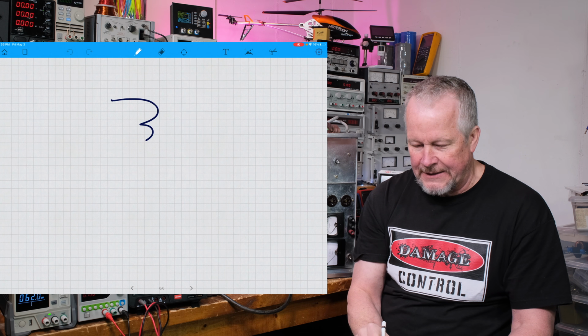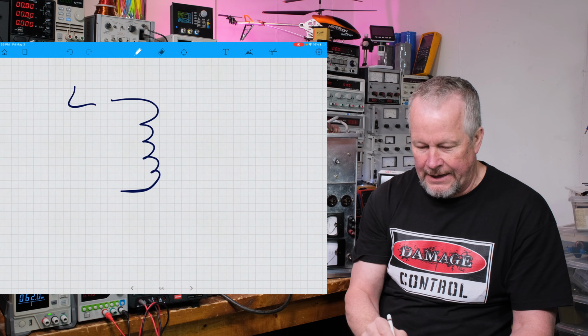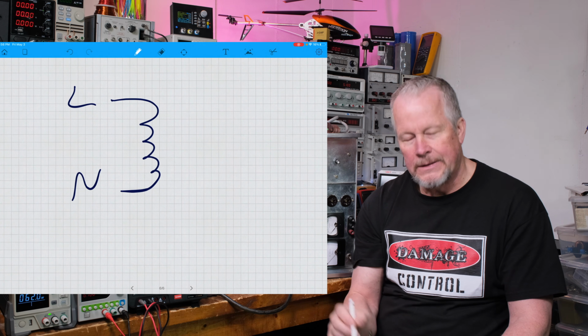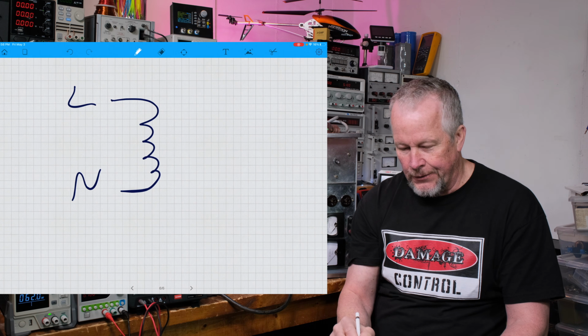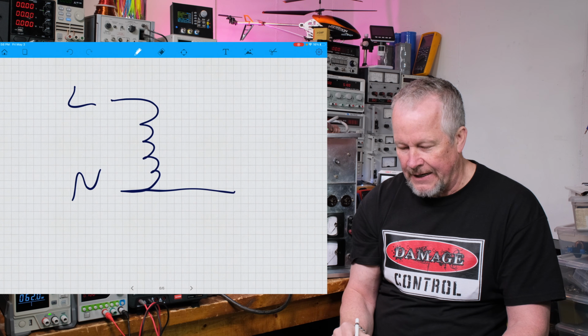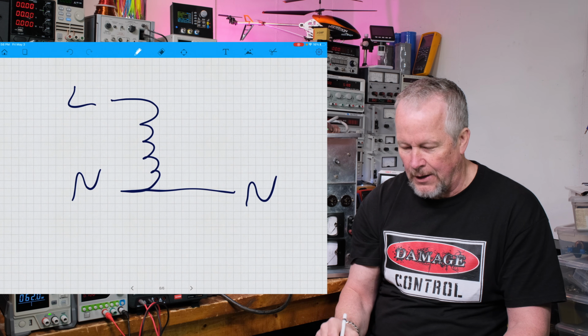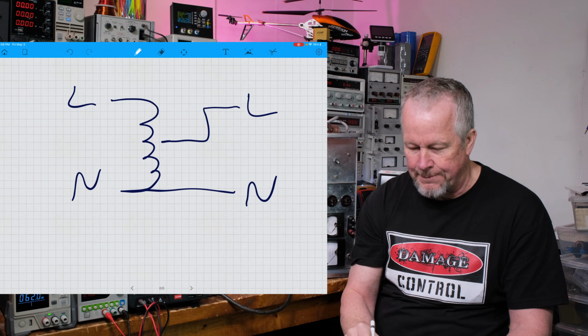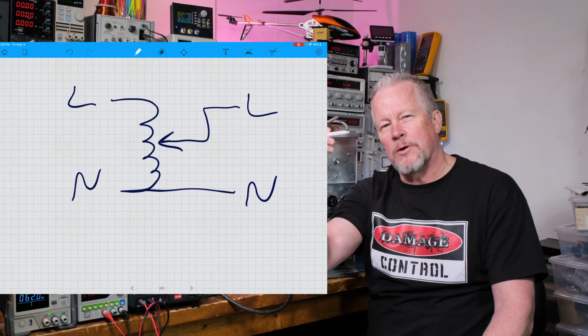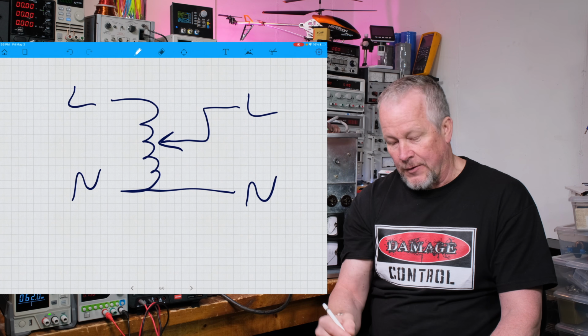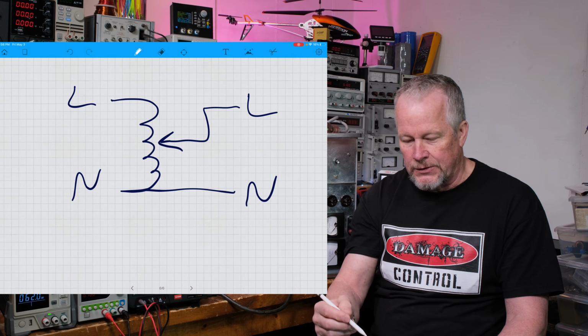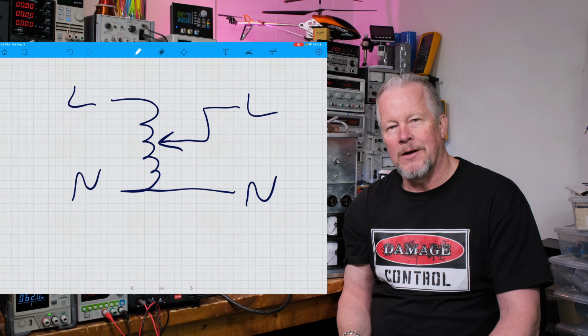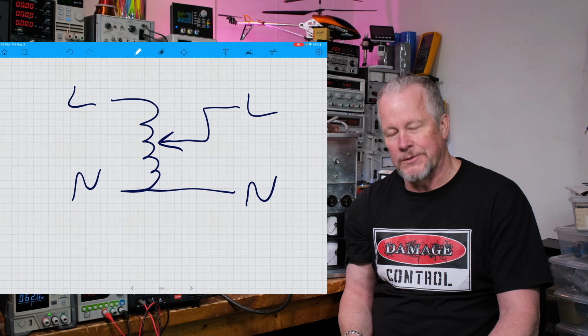Let me show you. It has a winding like this, and you have line and neutral. On the secondary side, where you take your power off, you have neutral, and line here is a wiper. That wiper goes up and down - if it goes down towards neutral, it's 0 volts. If it goes up towards the top, it's 132 volts or 120 volts.